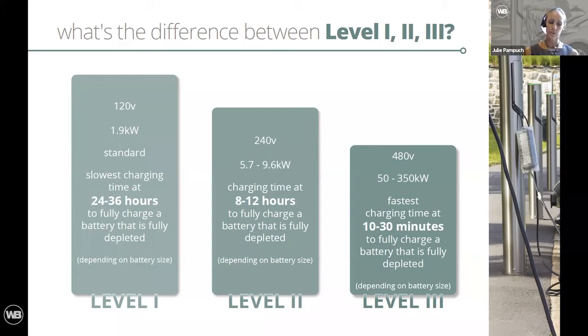DJ, what about the breaker sizes, the typical breaker sizes for the different levels? That's actually a good question, Julie, because it differs from level 1 to level 3. For level 1, it's just a standard outlet, so it's just your standard 20 amp breaker that you have in your house. For level 2, it's a 40 amp 2-pole. Rarely we've seen an 80 amp 2-pole, but it's generally a 40 amp 2-pole. So it's twice the size of your level 1 breaker. But both level 1 and level 2 can fit in a standard panel.